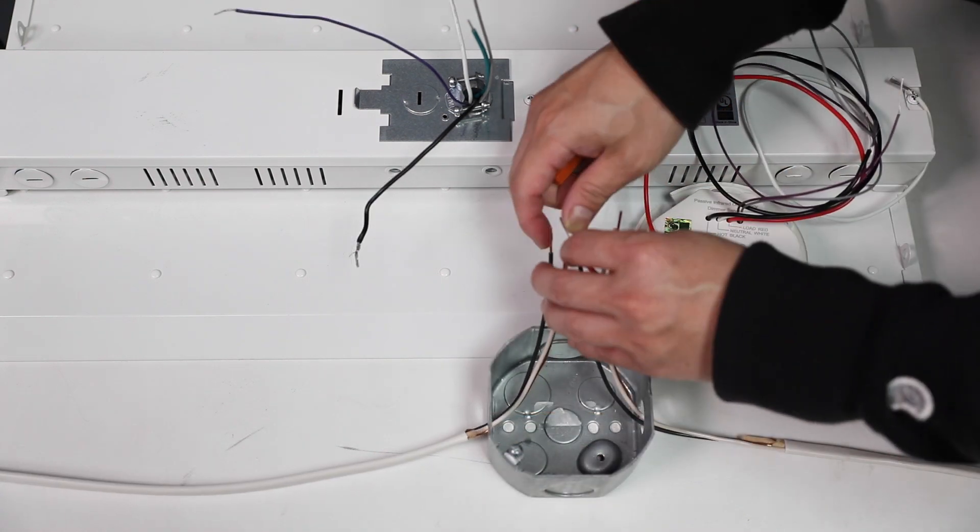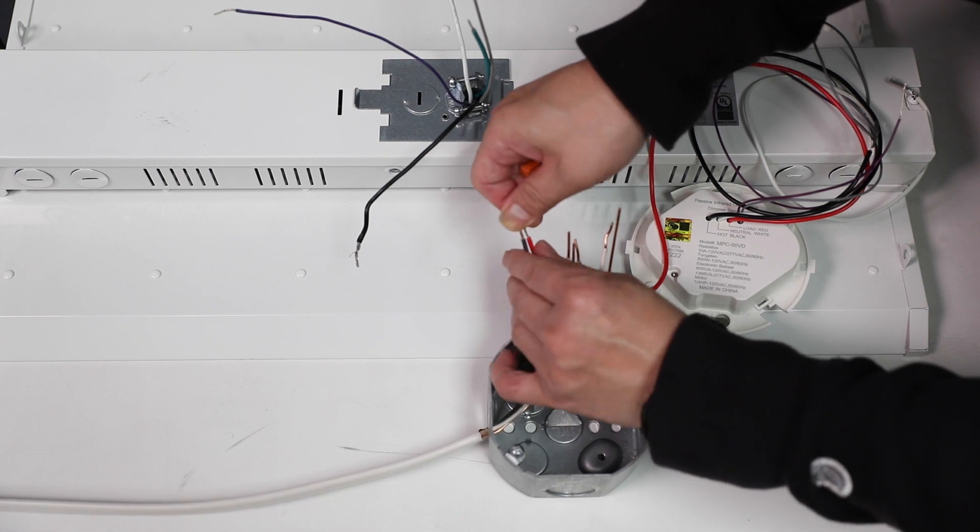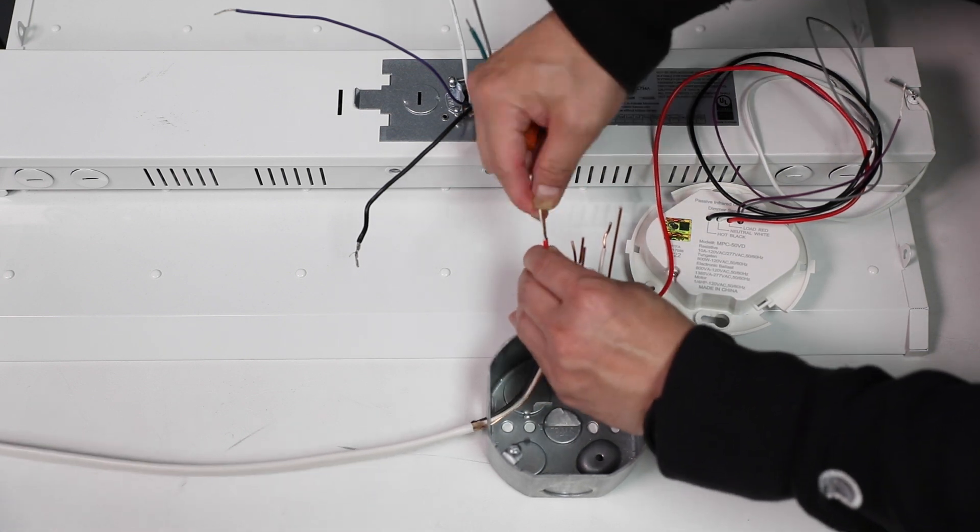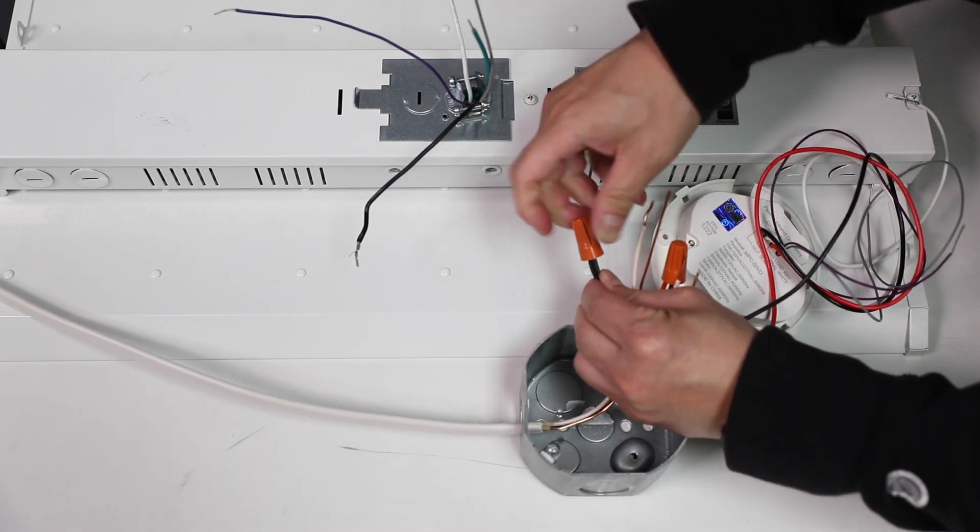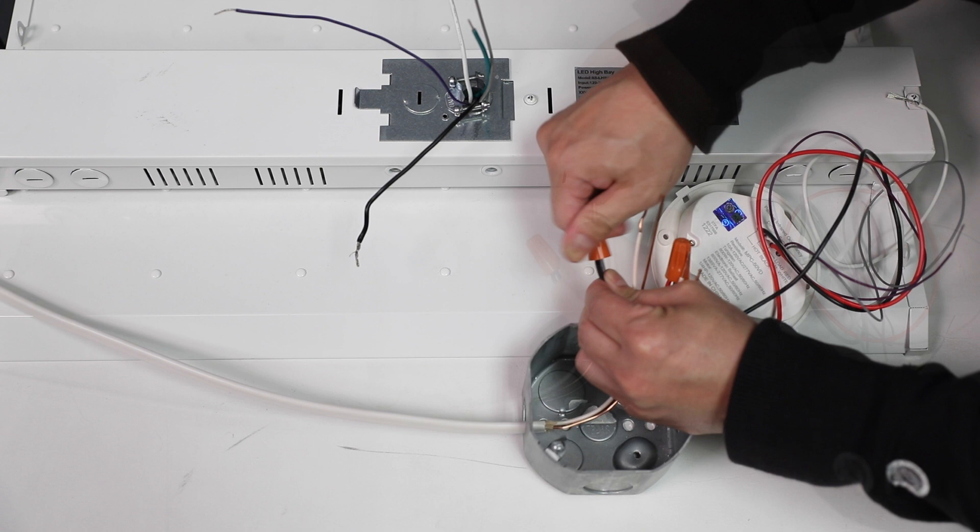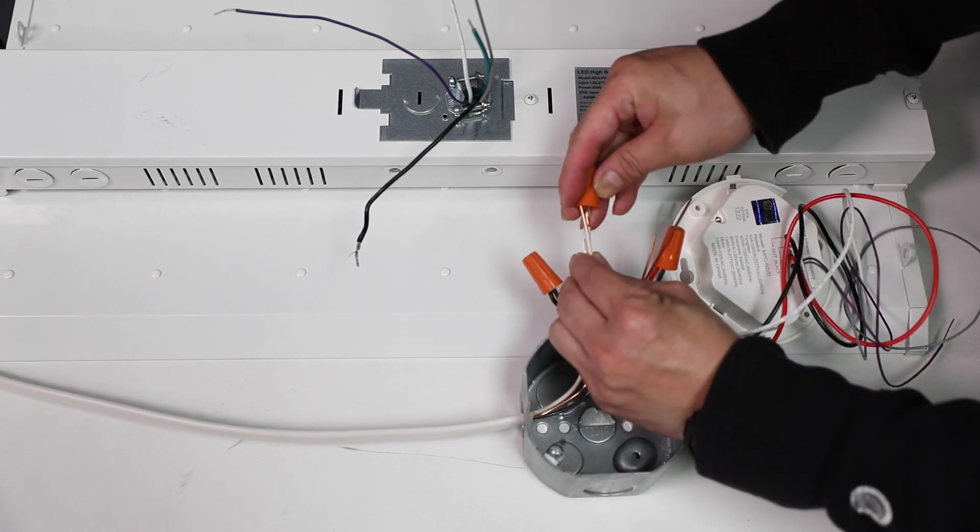Use wire nuts to connect the red wire on the sensor to the load wire, connect the black wire on the sensor to the hot wire, and connect all the neutral wires together.